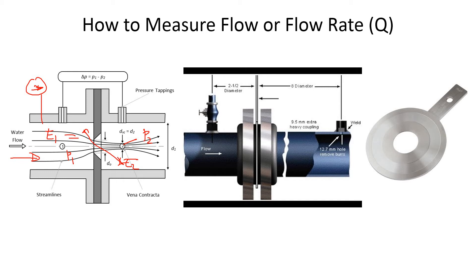If we have a standard orifice—an orifice is just a plate with a hole—you can place it here and calibrate it. We can send maybe a thousand gallons per minute and see how much pressure drop we observe.